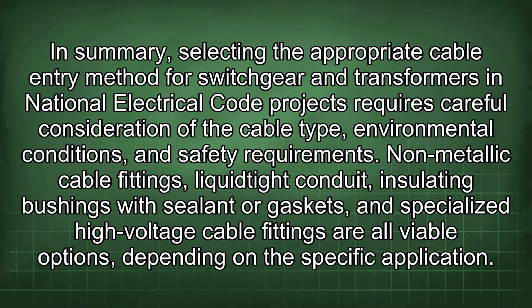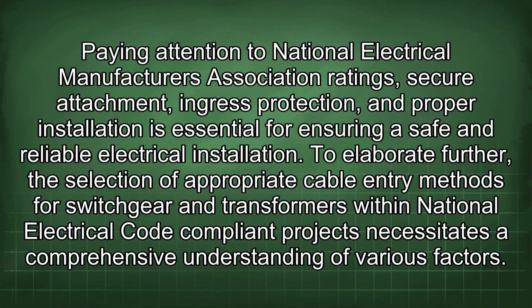In summary, selecting the appropriate cable entry method for switchgear and transformers in National Electrical Code projects requires careful consideration of the cable type, environmental conditions, and safety requirements. Non-metallic cable fittings, liquid-tight conduit, insulating bushings with sealant or gaskets, and specialized high-voltage cable fittings are all viable options, depending on the specific application. Paying attention to National Electrical Manufacturers Association ratings, secure attachment, ingress protection, and proper installation is essential for ensuring a safe and reliable electrical installation.